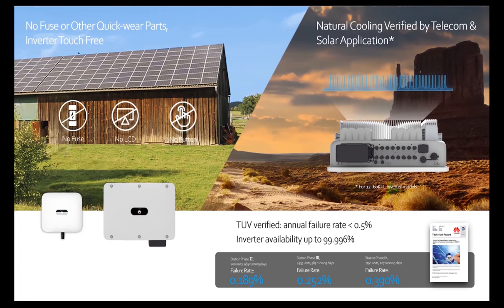So you can see in certain areas on the right hand side, the surface area is slightly larger and thicker, depending on where the hotspot areas of the inverters are, to ensure that there is sufficient surface area available for the inverter to cool itself naturally rather than using fan cooling, which typically allows external air to enter the internal electrical components themselves and reduces the lifetime of the inverter.